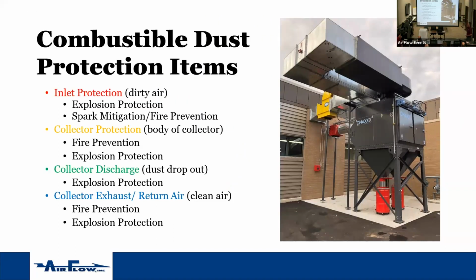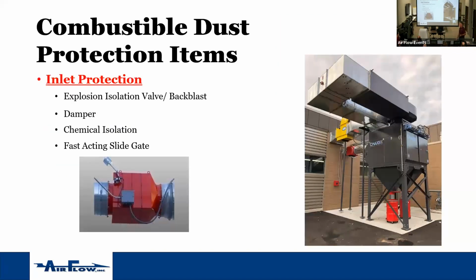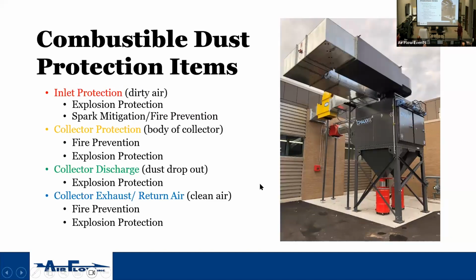So we'll run through this. So combustible dust protection items. You have inlet protection, your dirty air side. You have to protect it from explosion. You also have to protect it on the fire prevention side. You'll have your collector body itself. The protection of the collector, you'll have fire prevention, which will be sprinkler heads. Some insurance companies will mandate that you put a sprinkler head in it, even if it sits outside. Some will tell you they want a certain distance away from the building in the event that a fire does occur, that it doesn't affect the building itself.